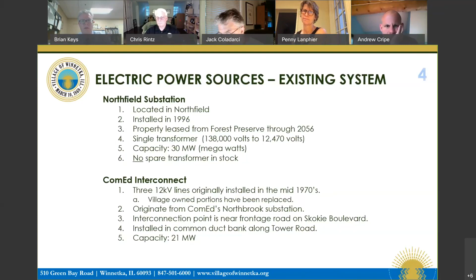We also get power from what we call the ComEd Interconnects. That's three 12 kV lines originally installed in the mid-1970s. Just for clarity, the village has replaced its section of these lines previously, so our cable is newer than the 1970s. This originates from ComEd's Northbrook substation. Two of the lines terminate at our South Load Center at Spruce and Berkeley, and one goes down to the power plant. Those cables are routed along Tower Road, and each one has a capacity of nominally 7 megawatts, for a total capacity of 21 megawatts. Next slide.